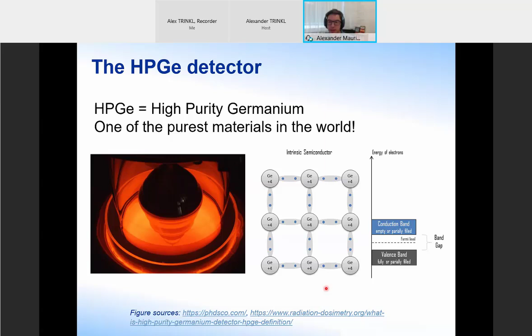And we will look now at what happens when the photon interacts in there. The detection principle of a high purity germanium detector, if we consider this PIN structure, so you have a P contact on one side and an N contact on another side, and then this sensitive intrinsic region in the middle, is that we first of all need to apply a reverse high voltage bias, so opposite of what the contact might suggest, of several kilovolts to make this intrinsic region, which is the region where it's actually sensitive to the incoming radiation, as large as possible. So if we have a gamma ray photon coming in there now, it knocks away one primary electron by, let's say, for example, photoelectric effect or Compton scattering. That electron might ionize then several secondary electrons. In the end, we have quite a lot of charges which are free here.